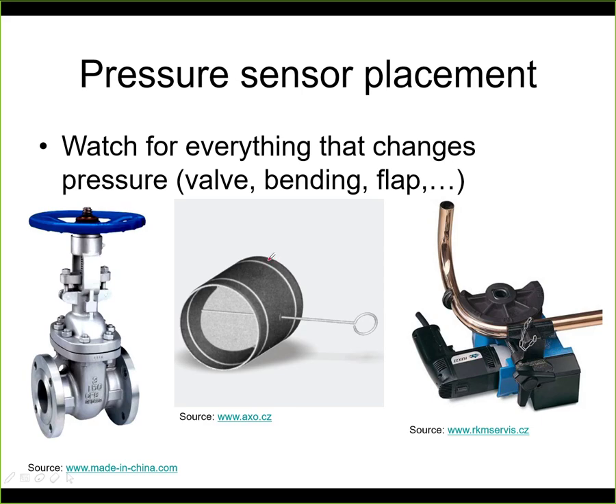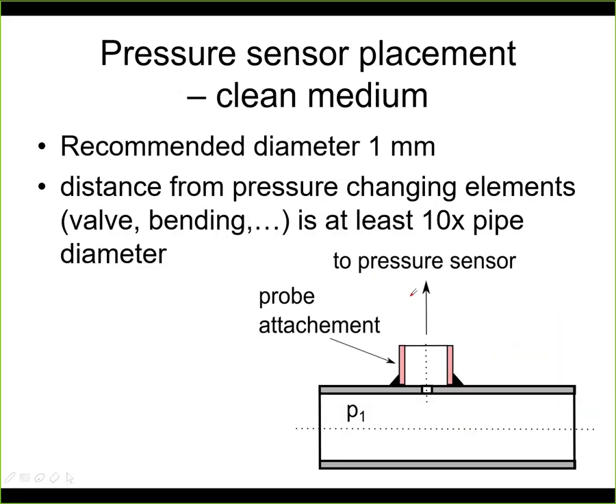Okay, at the end, let me discuss how to correctly install pressure sensors in some application, because it's quite important to install the sensor correctly. If you do not install the sensor correctly, it will measure something, but it may not be necessarily what you need to measure. So the first problem might be caused by anything that can change the actual pressure. You can imagine that it could be a valve, it could be a flap, it could be a bending like this, and anything that changes the pressure will actually have an influence on your measurement. So there is a rule how far should your pressure gauge be installed from those elements. So let's take a look at that.